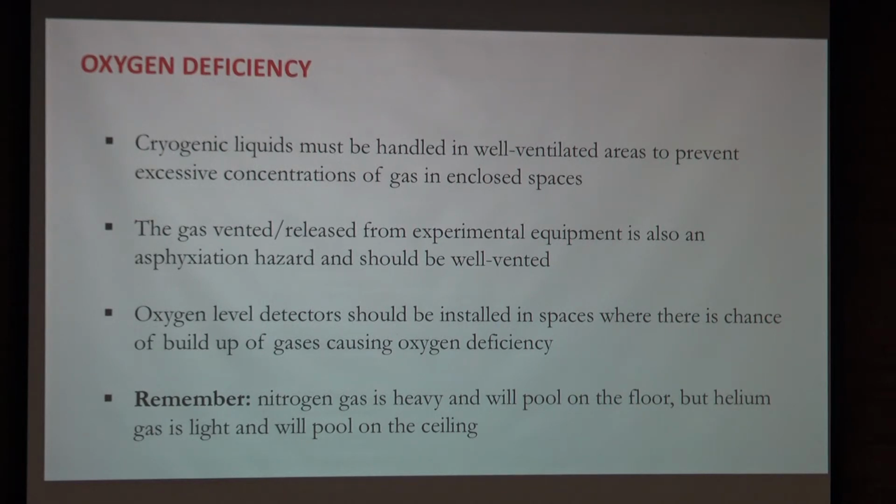So you want to keep breathing above floor level. Liquid helium is the opposite. It is lighter than air, so it will start filling the room from the ceiling. So keep in mind which cryogens you're using, how they accumulate, and where you want to ventilate them out of your laboratory.